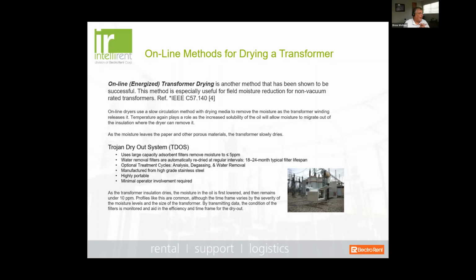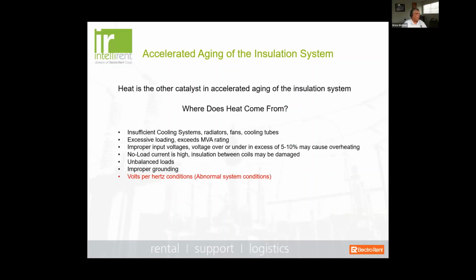So it does take some time depending on the amount of moisture and the size of the transformer. Also, if you have had a gassing problem and you've identified what that gassing problem is and you've corrected it, it will also degas the oil, goes through a degassing cycle as well. But it's highly effective and quite simple to use and self-monitoring, so you don't have to worry about broken lines or broken hoses, and you can actually monitor it online through a cell phone.